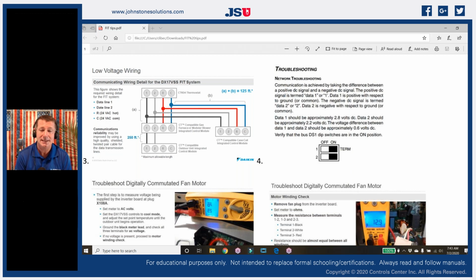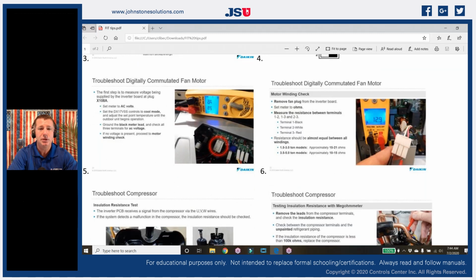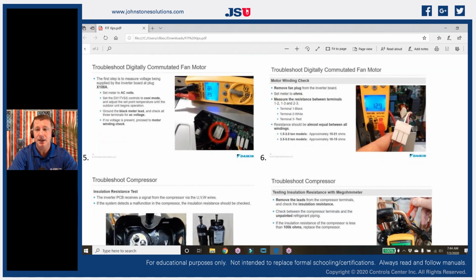If it gets below 0.6, I can actually turn on that bias and it's going to boost the differential between the 2 of them. So it's going to help change that differential so it can get to that 0.6 volts. But it's really critical to understand that on that Climate Talk, on that Comfort Net communicating system, if we don't have a 0.6 volt DC bias between the 2 of them, it's not going to communicate properly. So most of the problems that we run into with inverter technology and communicating technology is in the control wires. So it's just a matter of understanding how those things communicate.